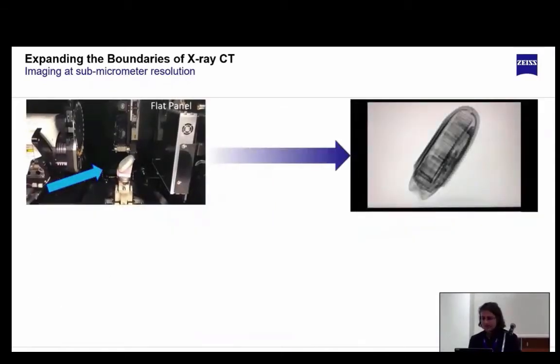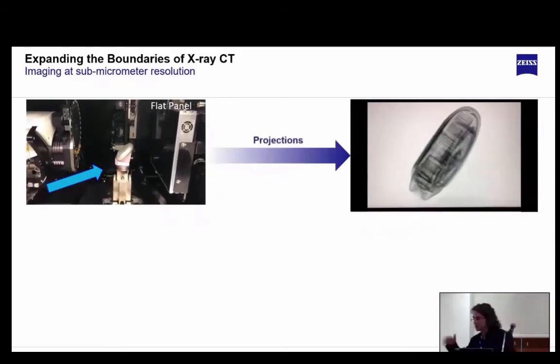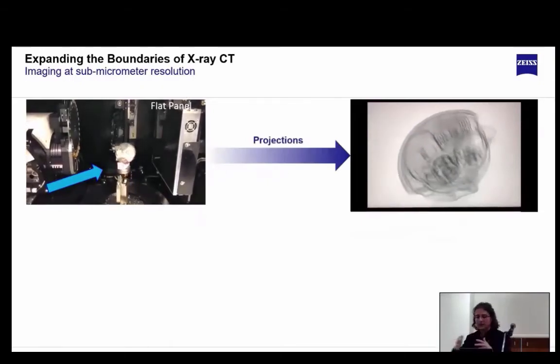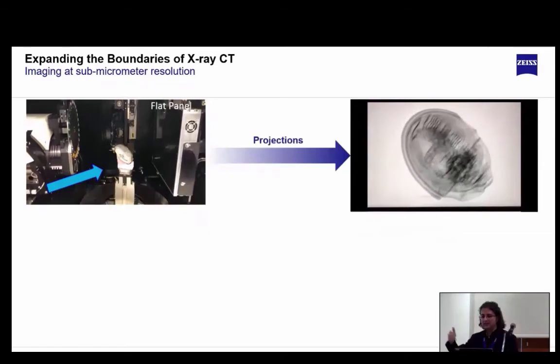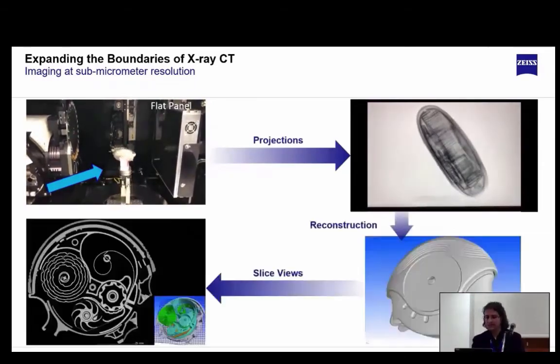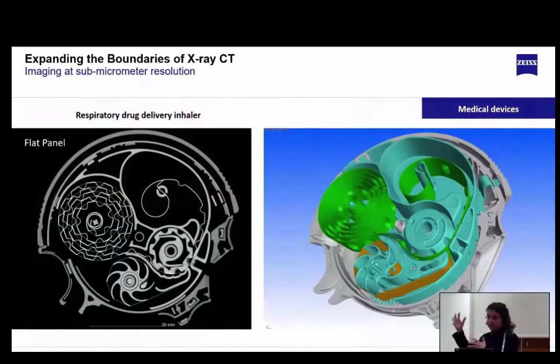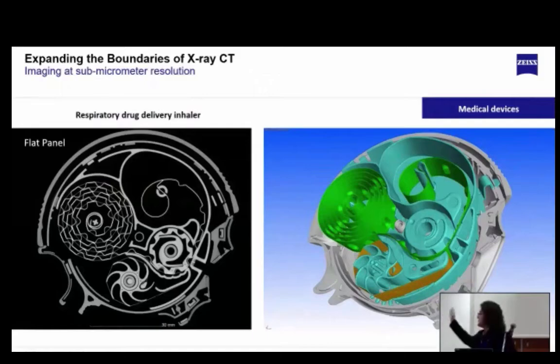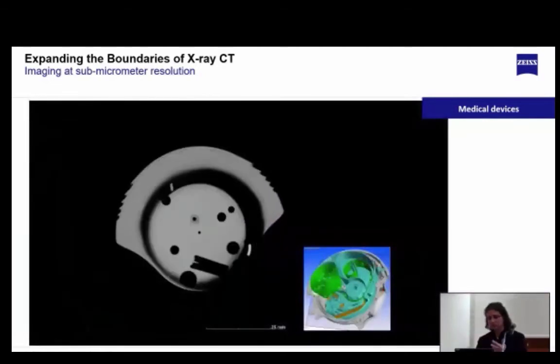And the full assembly of a medical device can be inspected also for a quick scan with a flat panel. You can add a flat panel to this optical microscope to make a quick scan of the full device and check the different assembly or components of the scan. And after doing the full 3D reconstruction, thanks to the high contrast capabilities that we have also in the flat panel, you can differentiate different material densities, even if they are very close to one another. And that allows segmentation, like the one that you see in the color map, and reverse engineering if you need to recreate a CAD model.